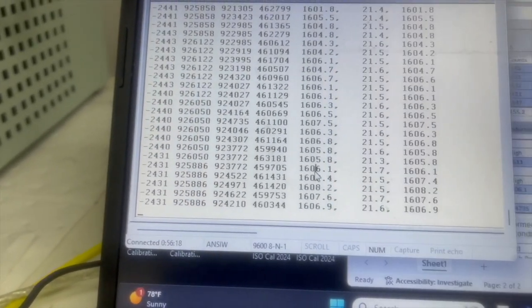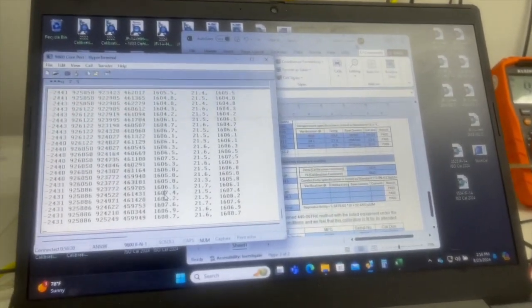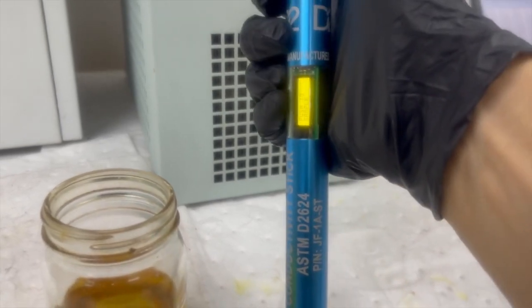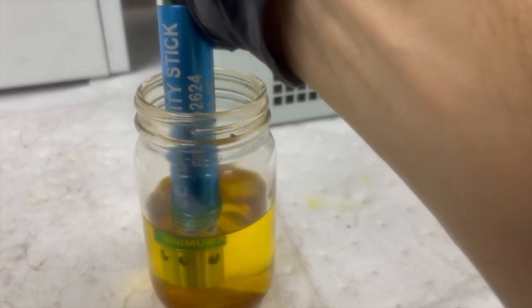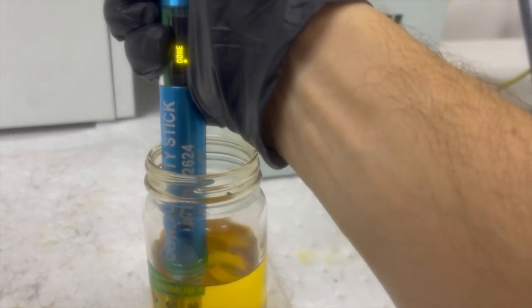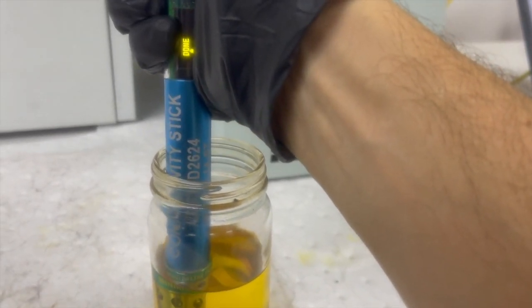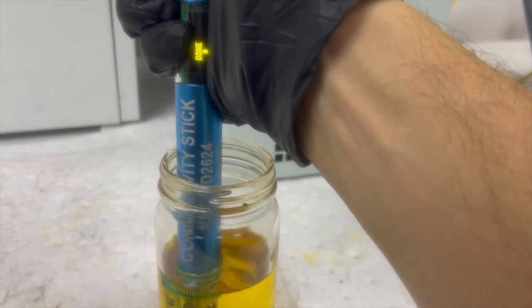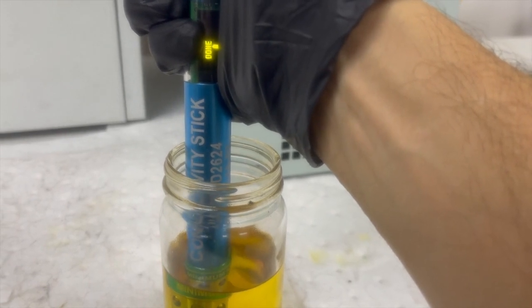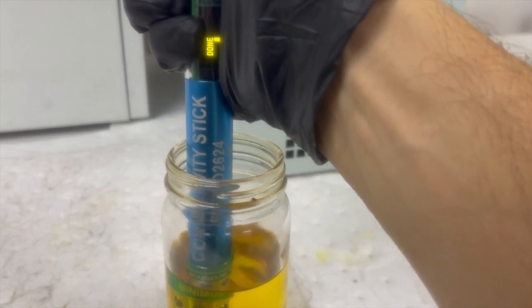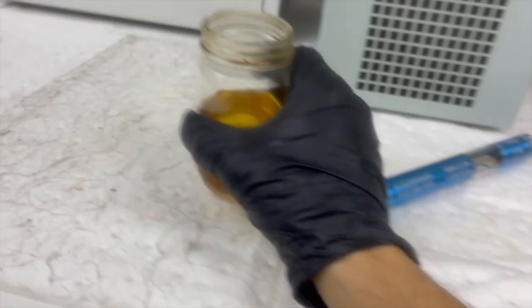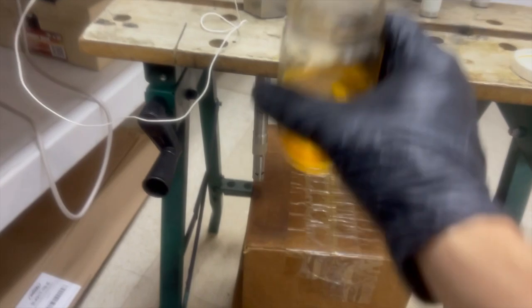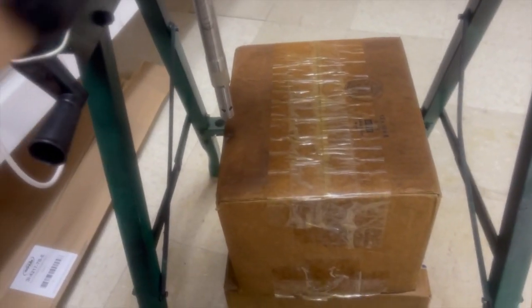And now we're going to verify the sensor is working properly. So to verify the conductivity, we're going to use our handheld. We're going to run it in the verification fuel sample and get a measurement. 1613. We're going to take this over here. We're going to get a sample on the inline sensor and verify.